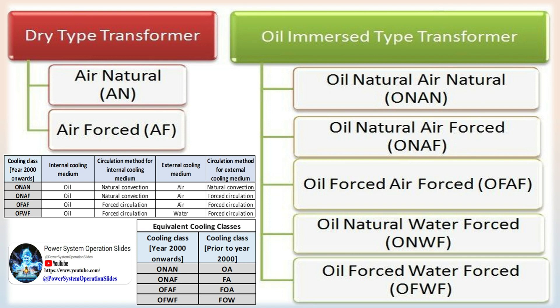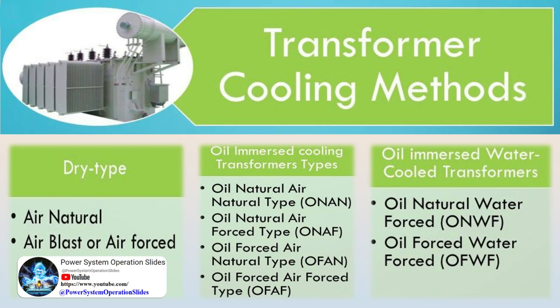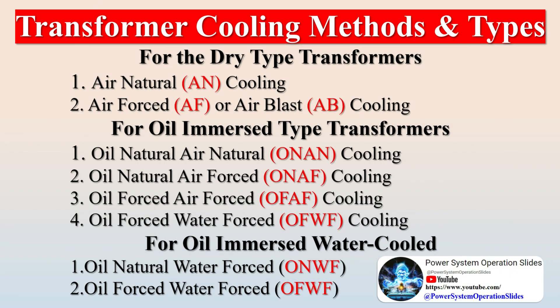Transformer cooling methods and types: For dry type transformers — (1) Air Natural (AN) cooling, (2) Air Forced (AF) or Air Blast (AB) cooling. For oil immersed type transformers — (1) Oil Natural Air Natural (ONAN) cooling, (2) Oil Natural Air Forced (ONAF) cooling, (3) Oil Forced Air Forced (OFAF) cooling. For oil immersed water cooled transformers — (1) Oil Natural Water Forced (ONWF), (2) Oil Forced Water Forced (OFWF).